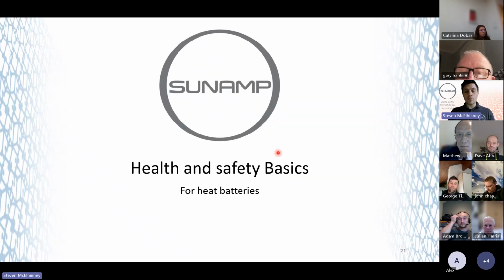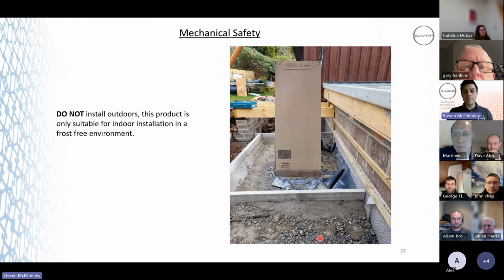So first of all, we've got health and safety. Obviously that's an over-exaggeration, but don't install the product outdoors. We do have an electrical element down here, and you've got an electrical control box up there. We do advise it should be fitted in an indoor installation in a frost-free environment. That's not to say you couldn't fit it in a weatherproofed outhouse, for example. But one thing you'd have to bear in mind is the heat losses would be much higher.